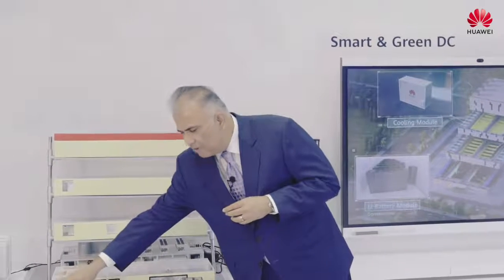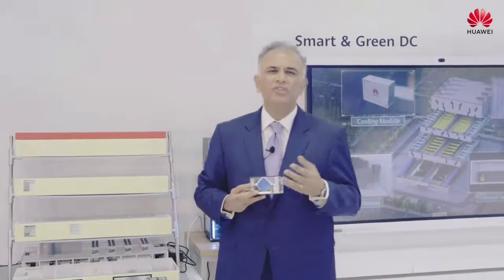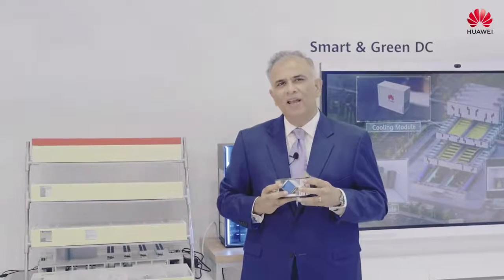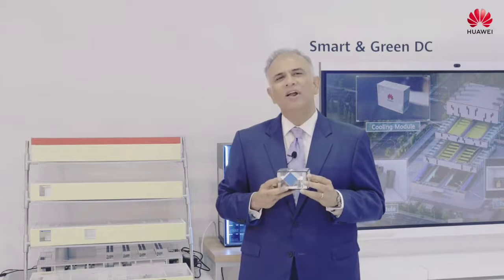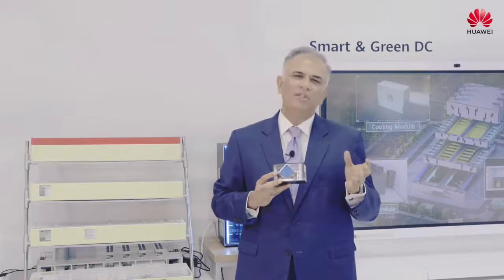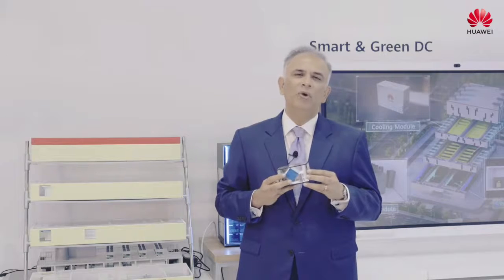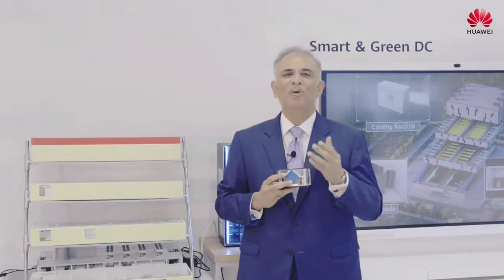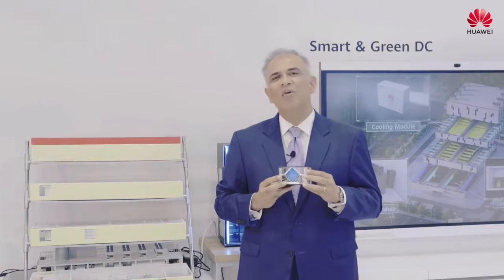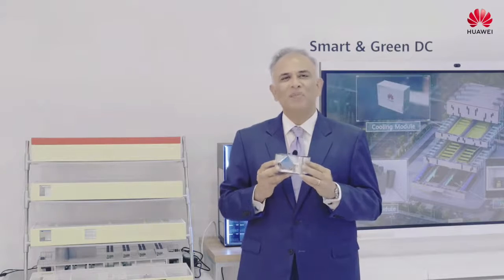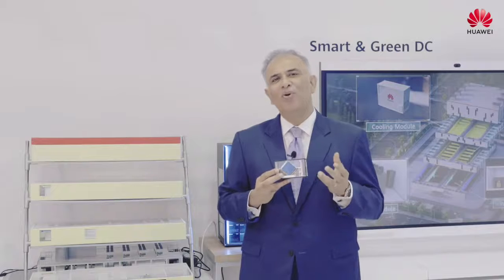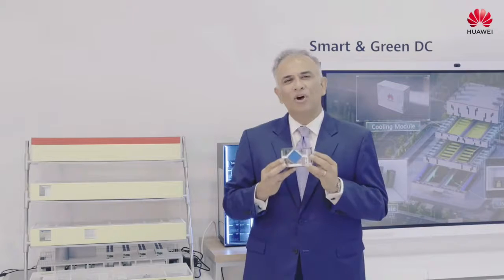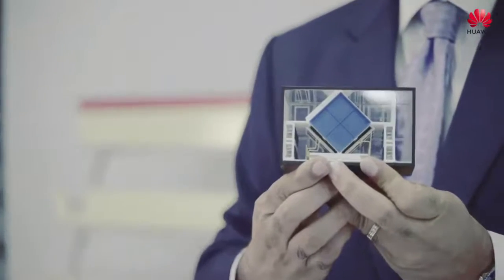On the cooling side, we've invested heavily in bringing higher efficiency and performance to our cooling solutions. Different geographies demand different cooling architectures and modules. At Huawei, we've worked on indirect evaporative cooling systems that help reduce PUE significantly. In countries like the Middle East, we've brought PUE down from 1.8-1.75 to as low as 1.3-1.35, mainly by leveraging free cooling, adiabatic cooling, and packaged DX, all pre-integrated into a module to create a cooling pod.